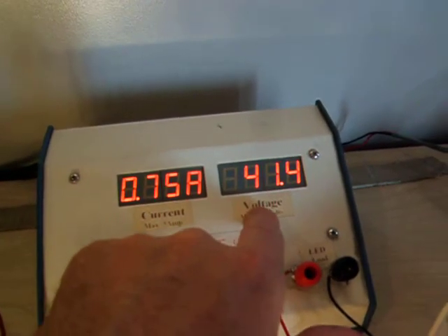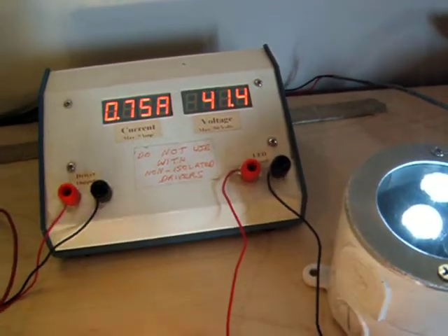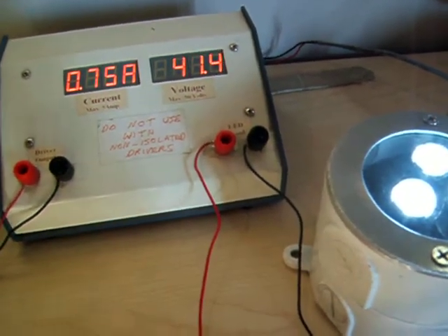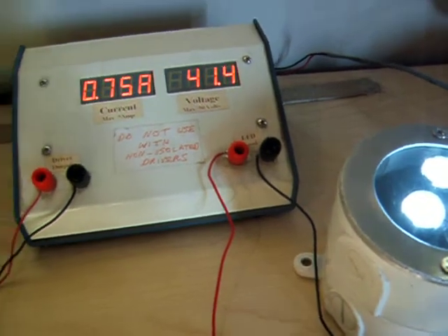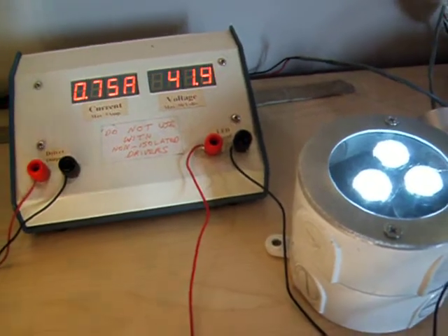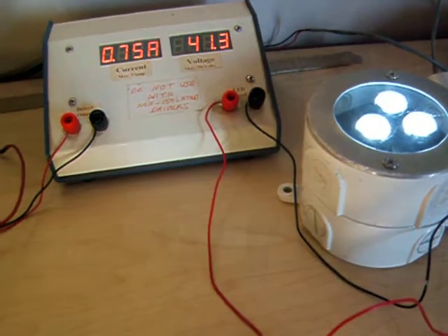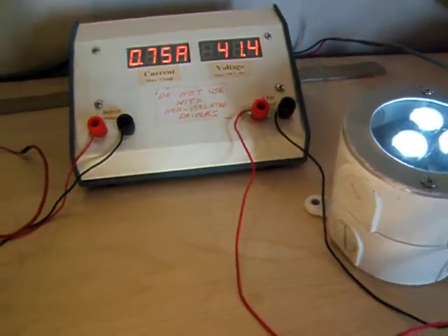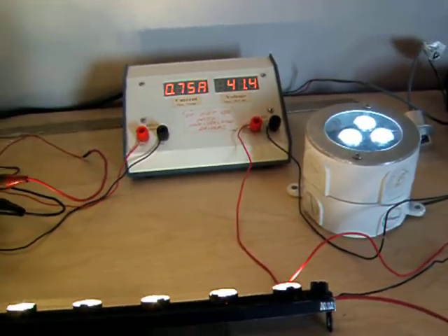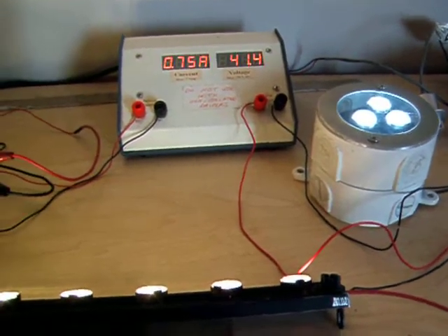The total load is 41.4 volts DC. So those 12 LEDs, if you divide 41.4 by the 12, that's an average of approximately 3.5 volts per LED, a little bit under 3.5. So if I added another one, I'd expect it to add another 3.5. Although when I am doing an installation, I always recommend people size 4 volts per LED when driven at 350 milliamps. So I'd actually size it a little bit higher since it's at 750.